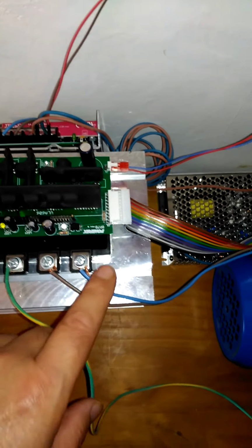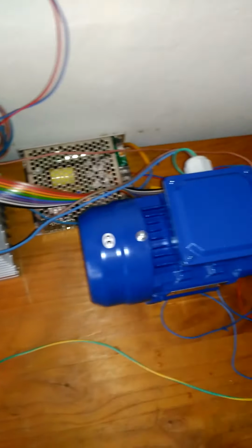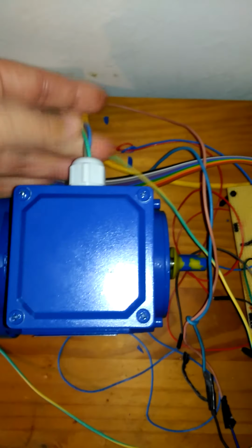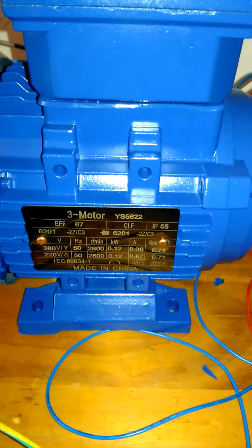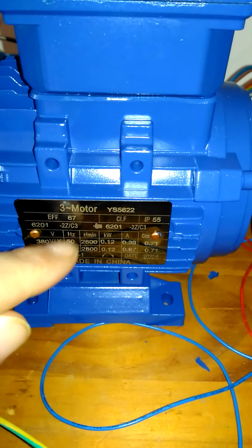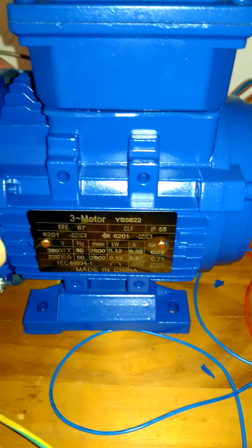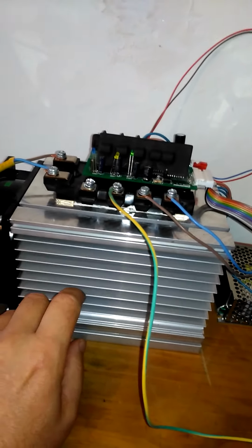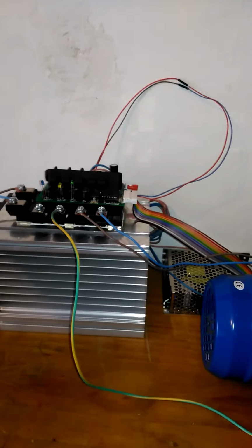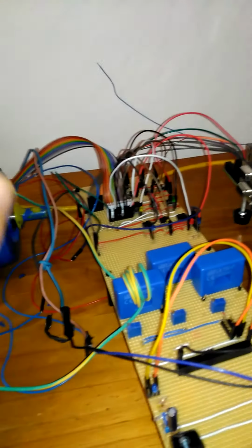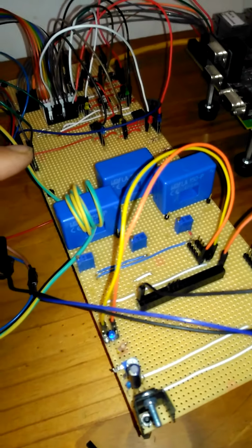This is the motor supply, so it's RST or UVW, L1, L2, L3, whichever way you want to call it, going to our motor here. A 3-phase polyphase induction motor, asynchronous, 120 watt, delta connected, and there's the nameplate of it. It's perfectly adequate for what I'm doing over here, because the control algorithm can work on a small motor or a big motor. It's all dependent on the size of the power device, really. I could probably haul 30 kilowatts out of this at the moment, well, when I get the DC bus to full capacity. But anyway, coming back to this variable board over here.